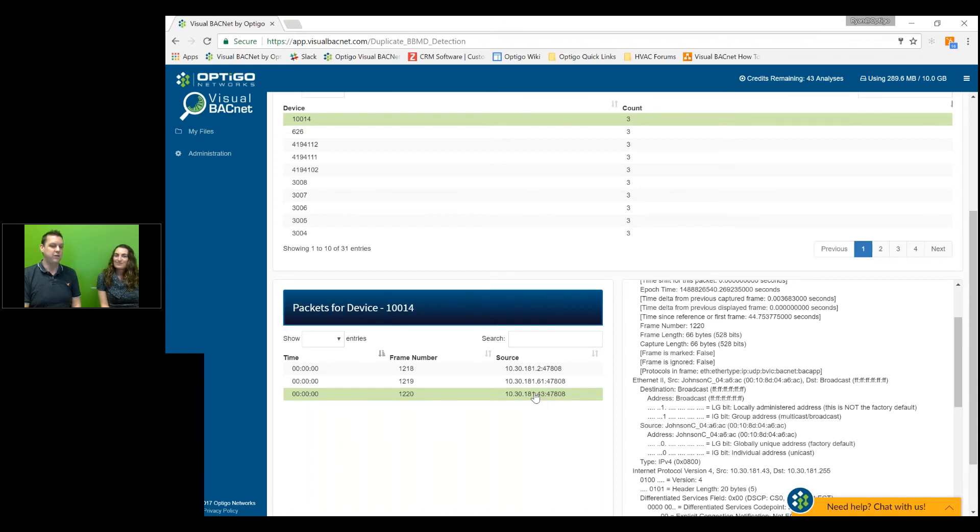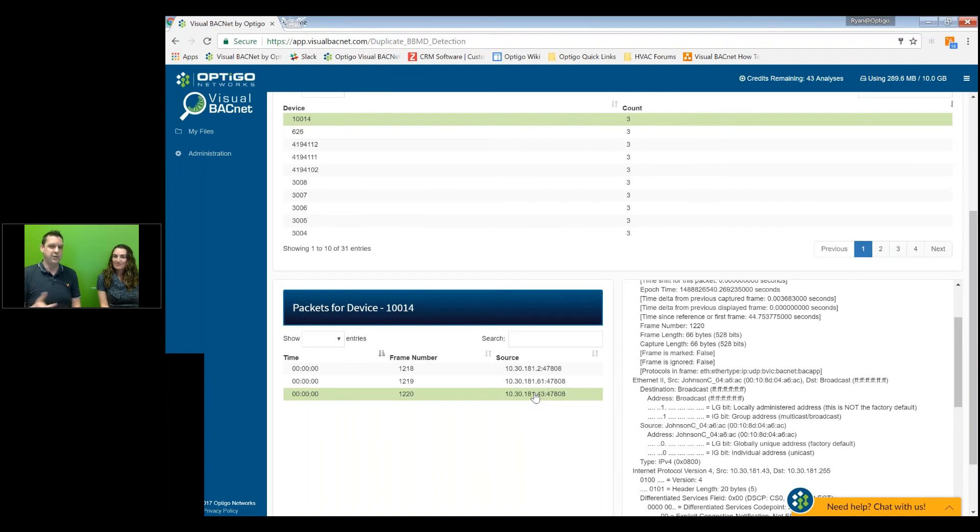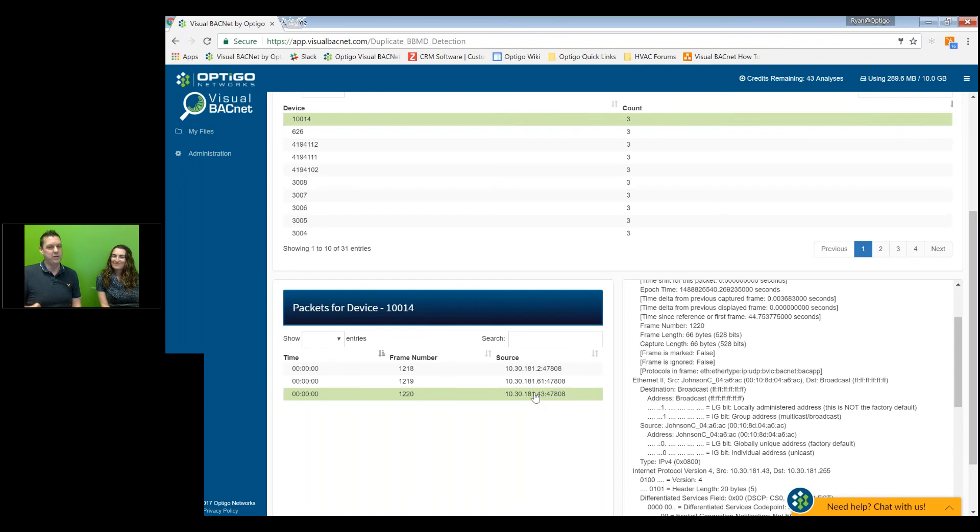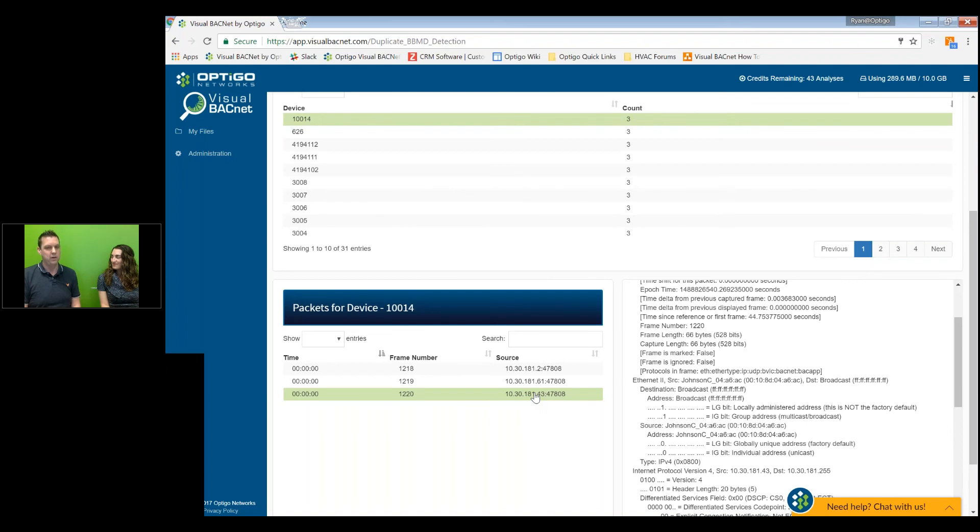Well, you can either do, there's a couple of things you can do. You could isolate the networks. But if you have an integrated site, which we assume you would, that's not really going to work for you. What you can do is you can either turn off two of the three BBMDs and have just one. Or you could turn them all off and put in a new controller to handle the BBMD functionality.